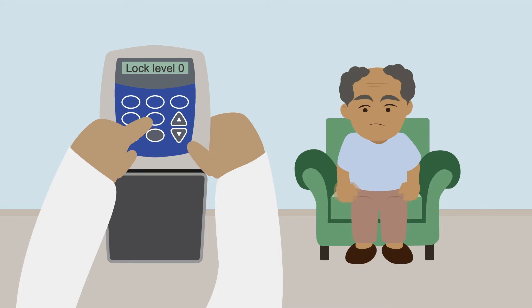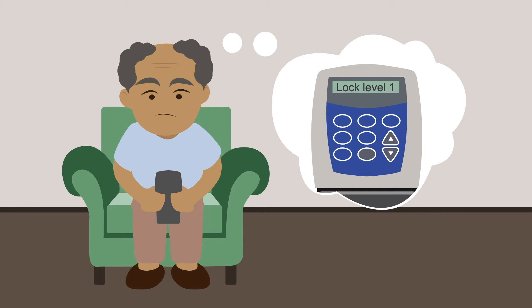Lock level 0 allows full access to all programming and is the setting that you'll use to program the pump. Lock level 1 allows the patient to be able to increase or decrease the continuous infusion during the day based on their symptoms.